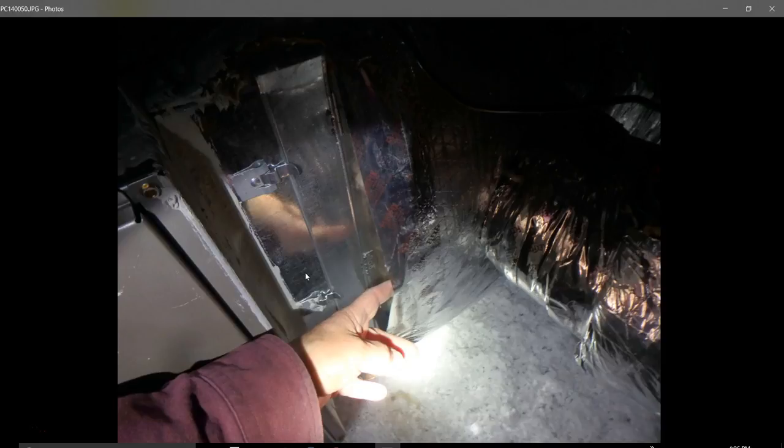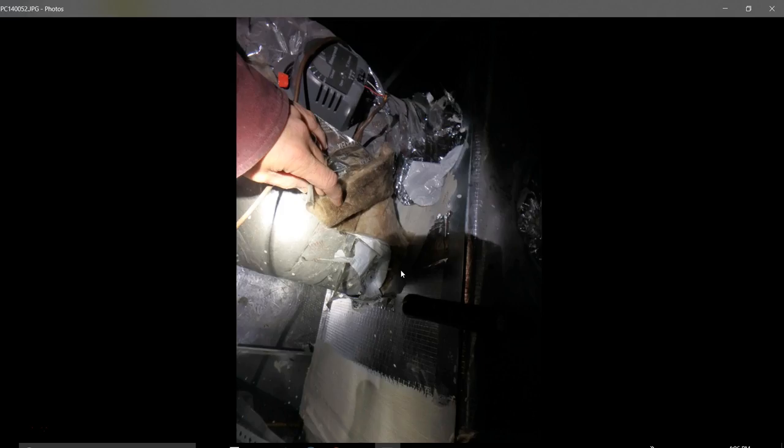Okay, yeah. This is the loose insulation. That's leaking cold and hot air into the attic; it needs to be taped back down. Oh, okay. This is the filter. Looks like you've done a pretty good job. It's a little dirty. Yeah, I'm replacing it. I just had to get up there. This is, again, some ducting that has loose insulation. They need to take that back in place.